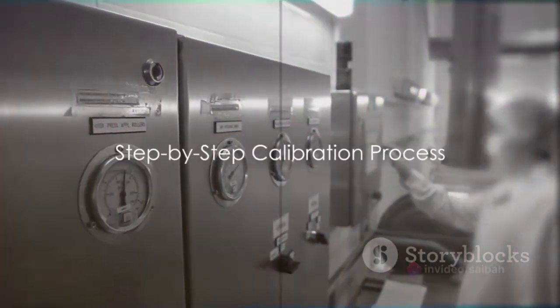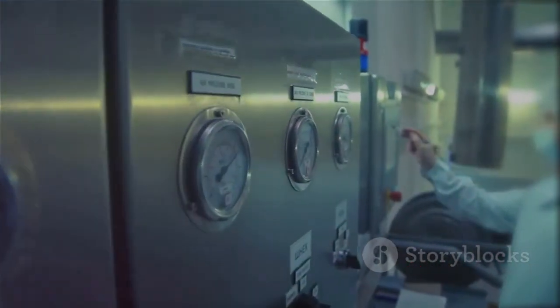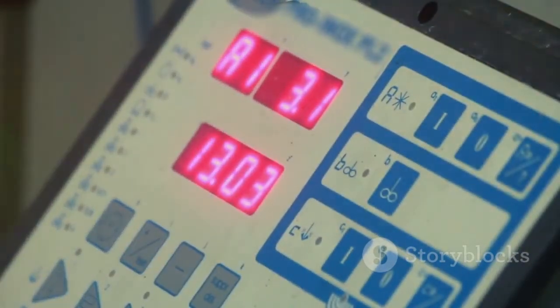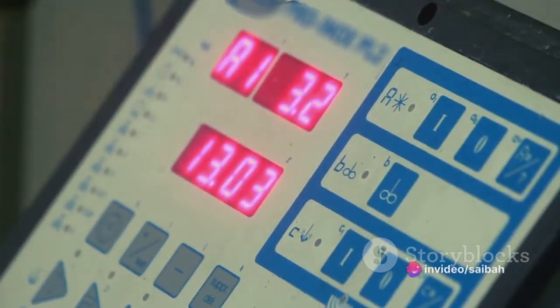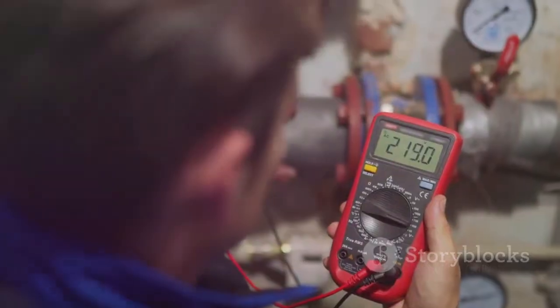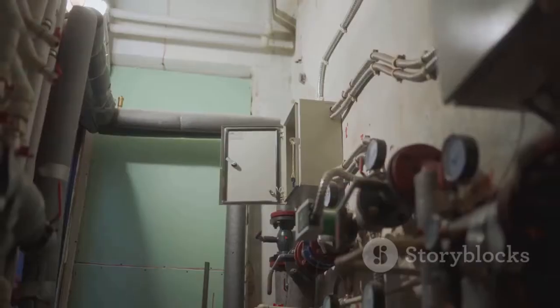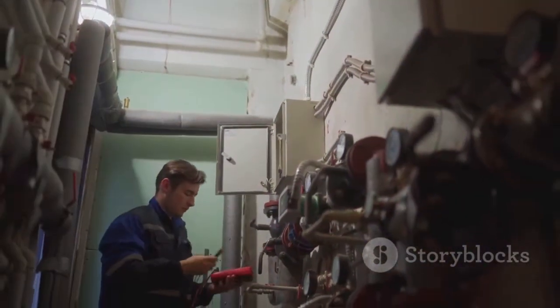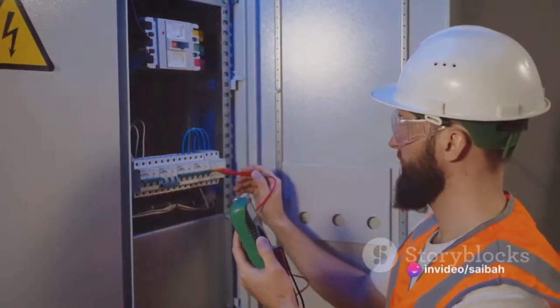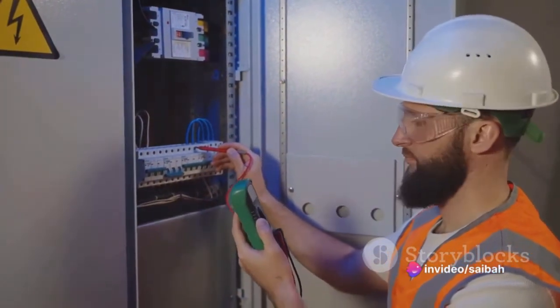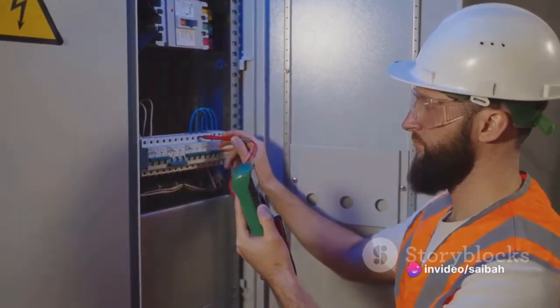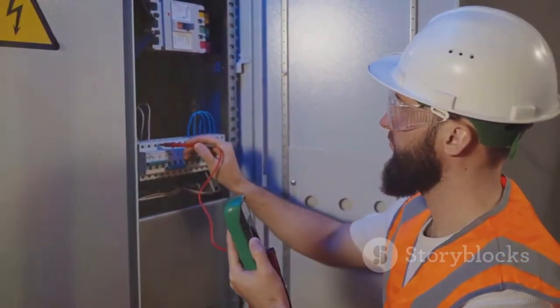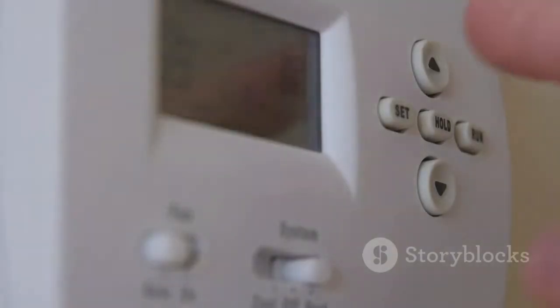Now, it's time to start the calibration process. This is where the magic happens, where we make sure our temperature switch is giving us accurate readings. So, let's roll up our sleeves and jump right in. The first order of business is to connect the temperature switch to the heat source and the multimeter. The heat source provides the heat we need to test the switch, while the multimeter helps us measure the temperature at which the switch trips. Make sure all your connections are secure, because a loose connection can throw off your readings. Once everything is connected, we're ready to start increasing the heat.